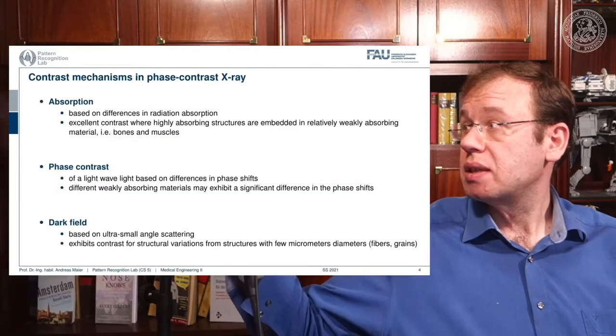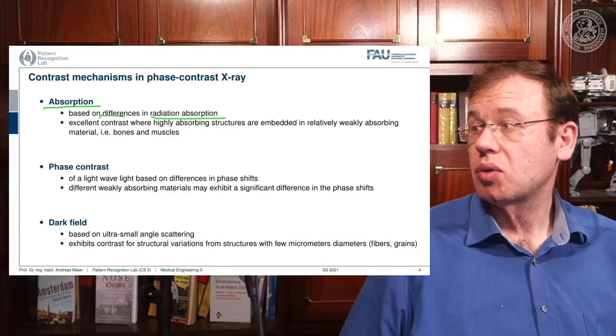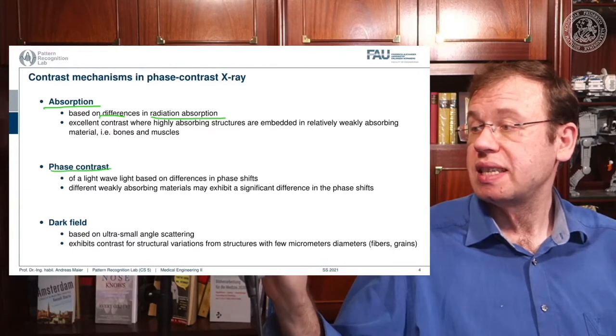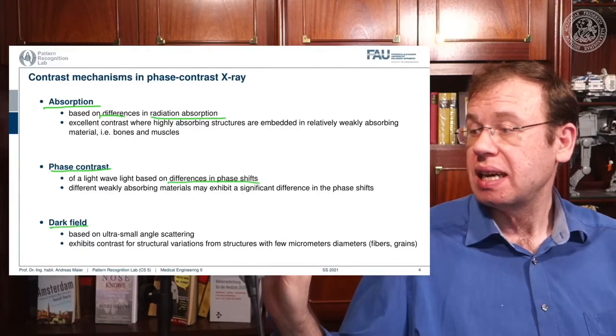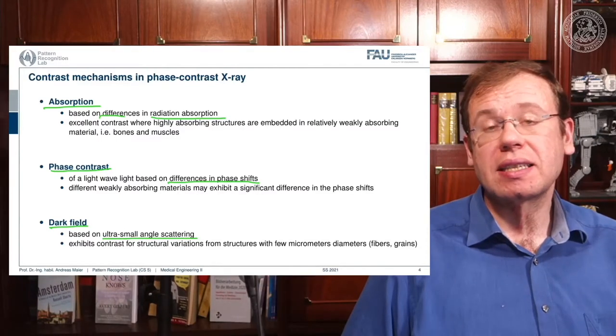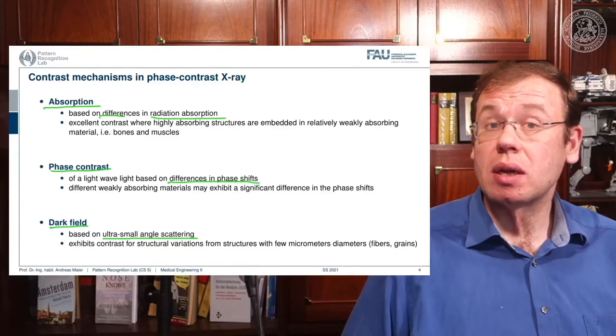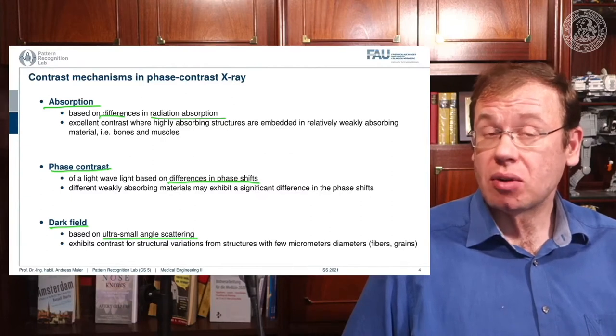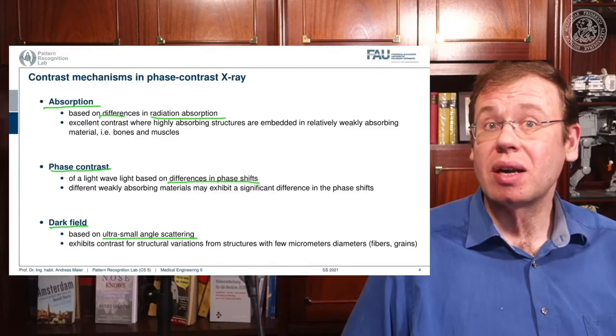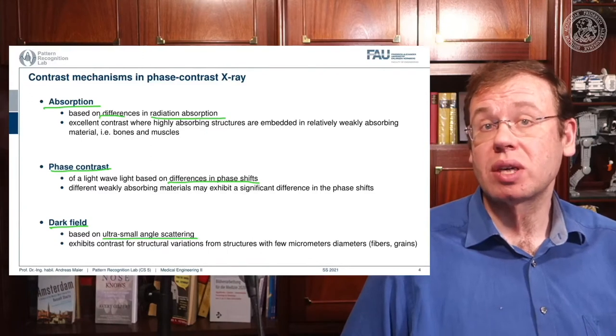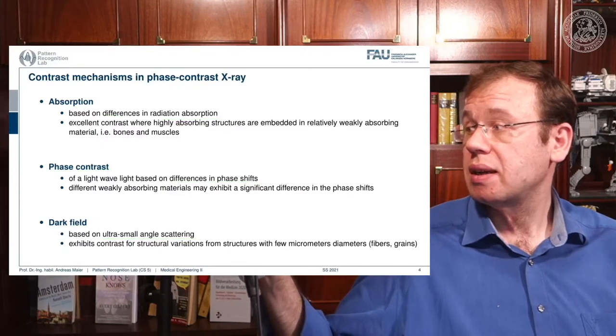To summarize: in the absorption image we see differences in radiation absorption; in the phase contrast image we see differences in phase shifts; and in the dark field we see ultra-small-angle scattering caused by microscopic structures that are way smaller than the actual detector pixel or reconstruction voxel grid. We can measure effects that are an order of magnitude smaller than the actual reconstruction scale. We'll see some very interesting results towards the end of this video.